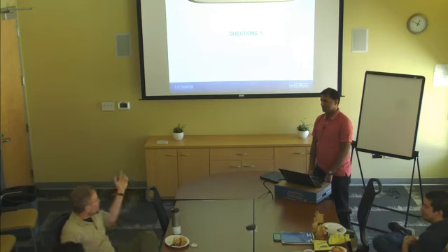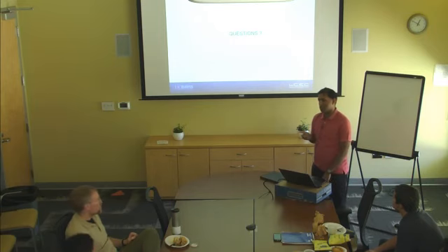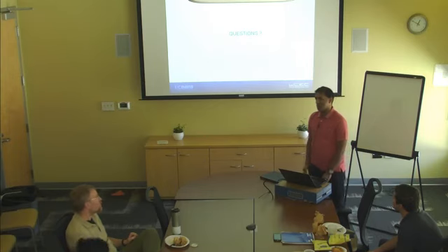So, is one of your takeaways that more than two zones doesn't get you a better payoff, that just two zones is optimal? Yeah, so one of the drawbacks of going to a lower number of zones is increasing the fan power, because we increase the pressure rise through the fan, and that actually creates a drawback.